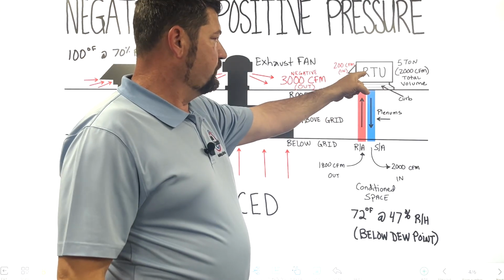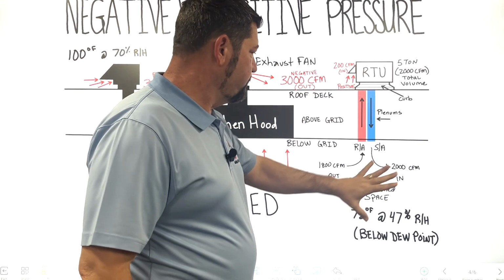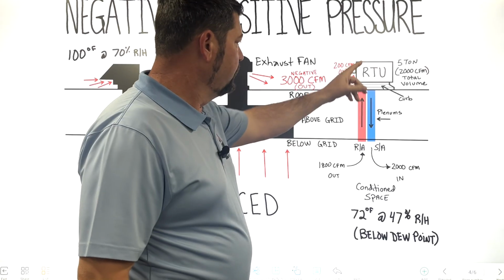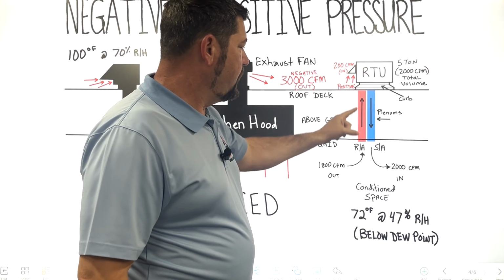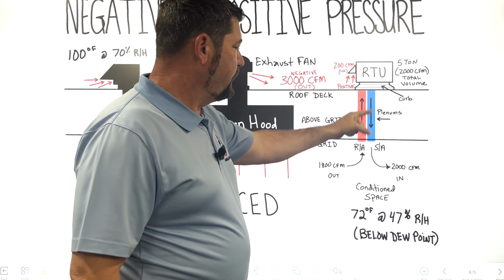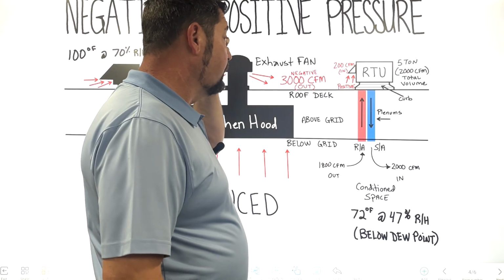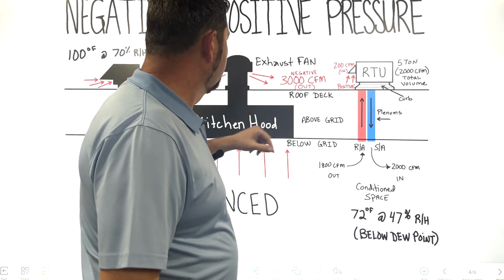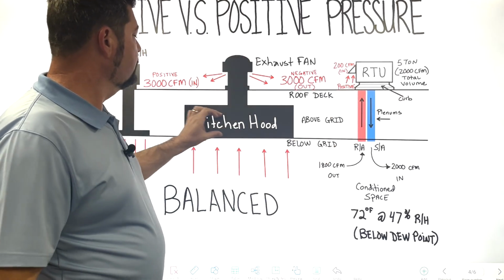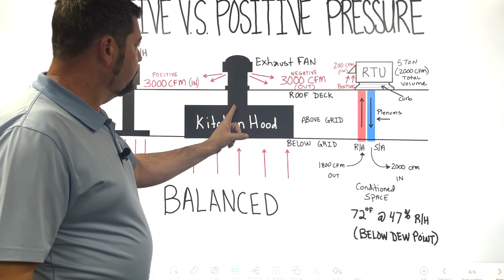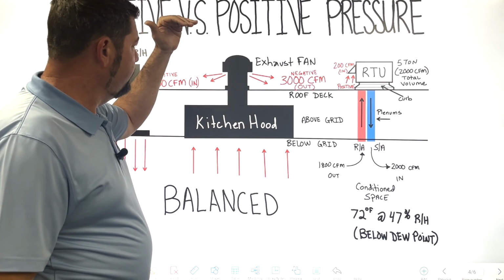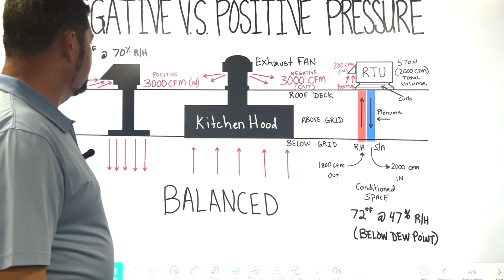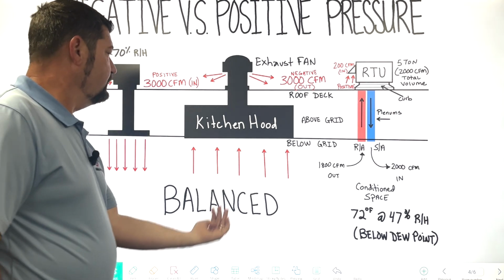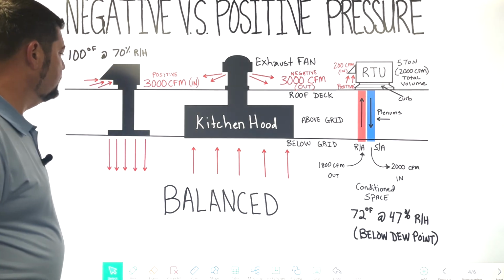And then again, here's our RTU. Now I drew some specs up here. We'll go over those. But we have our RTU, we have our return and our supply plenums here, right? Our curb. Now we have a kitchen hood here. And then we have the grease duct going up, and then we have the exhaust fan on top, which is exhausting the air that the hood is pulling up from the kitchen.